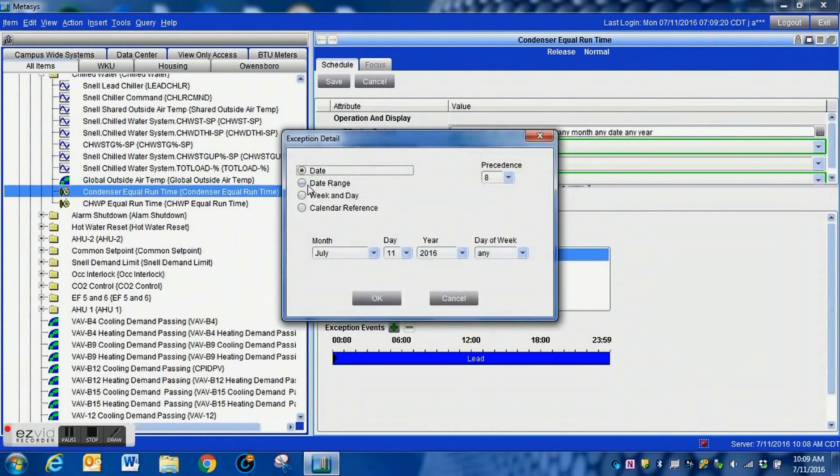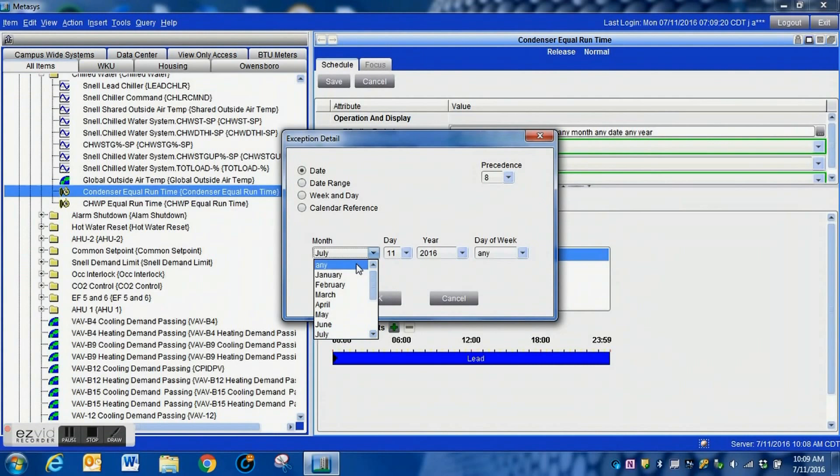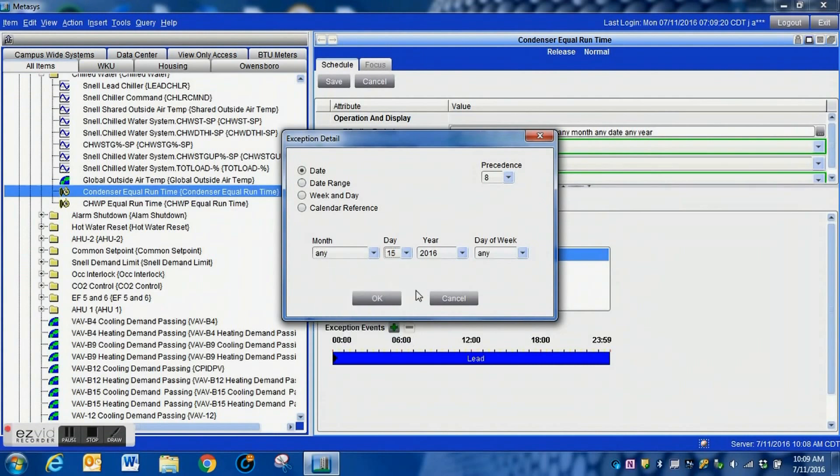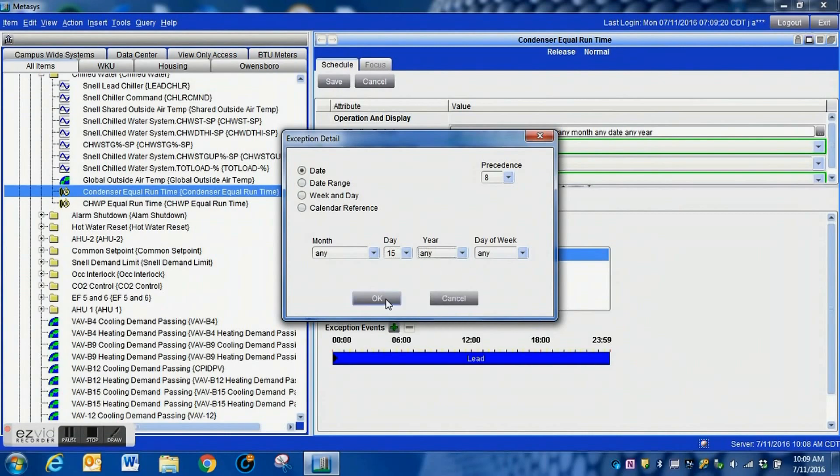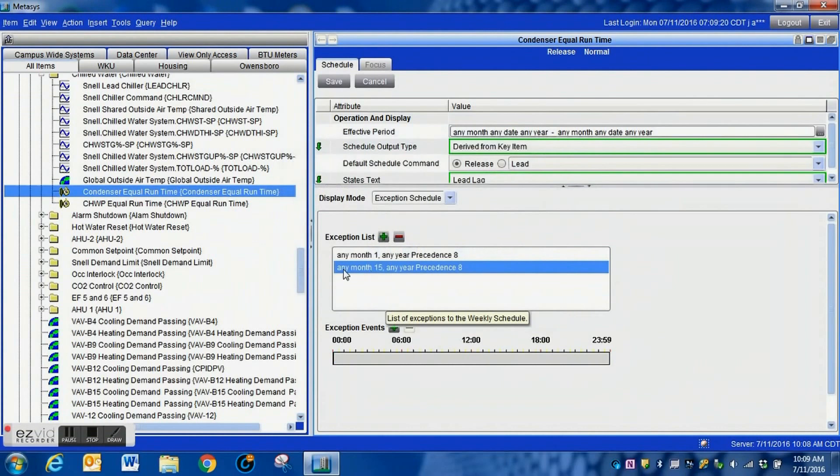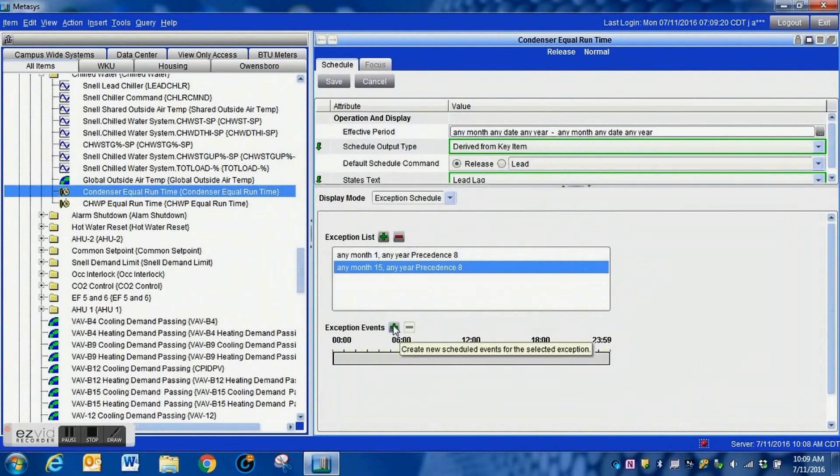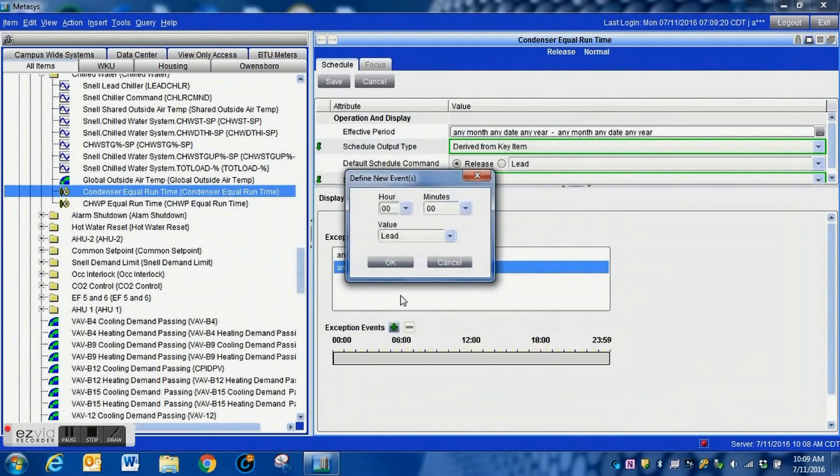Now on the here is our first one. We have it set up for the first of the month and we're going to have it simply set up to switch to lead during the first of every month. Now then we're going to go back into this, we're going to select date again. We're going to select the month to any, we're going to select the day to the 15th of every month, and of course we're going to set the year to any also.